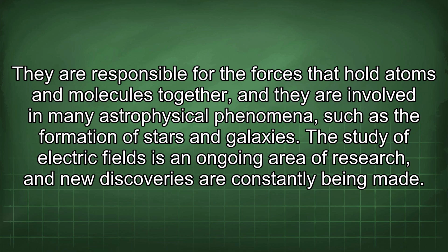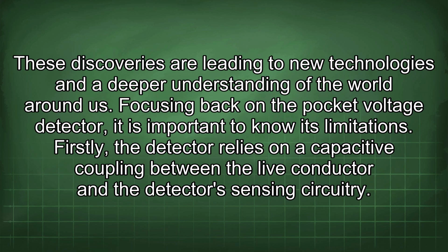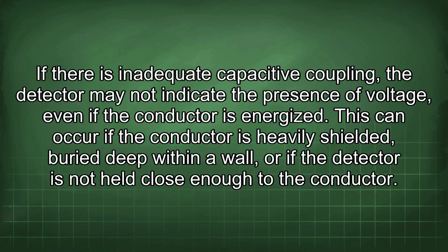The study of electric fields is an ongoing area of research, and new discoveries are constantly being made. These discoveries are leading to new technologies and a deeper understanding of the world around us. Focusing back on the pocket voltage detector, it is important to know its limitations. Firstly, the detector relies on a capacitive coupling between the live conductor and the detector's sensing circuitry. If there is inadequate capacitive coupling, the detector may not indicate the presence of voltage even if the conductor is energized. This can occur if the conductor is heavily shielded, buried deep within a wall, or if the detector is not held close enough to the conductor.